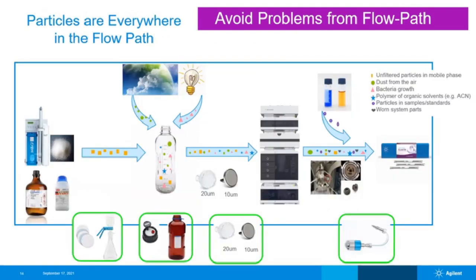Particles are everywhere in the flow path. They are accumulated in the flow path. They end at the column or the detector. Here we can list the unfiltered particles in the mobile phase, the dust from the air, bacteria, the polymers from organic solvents, the particles from the sample or the standards, the worn system parts. Particles are responsible for most of the issues in an LC system.